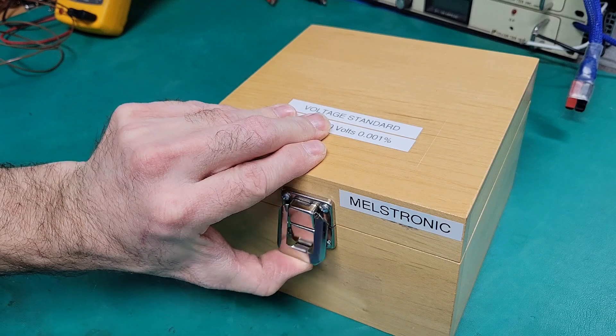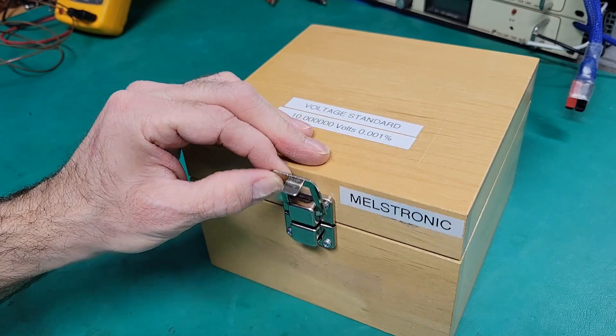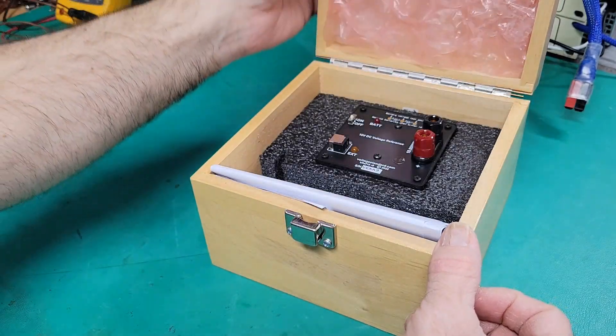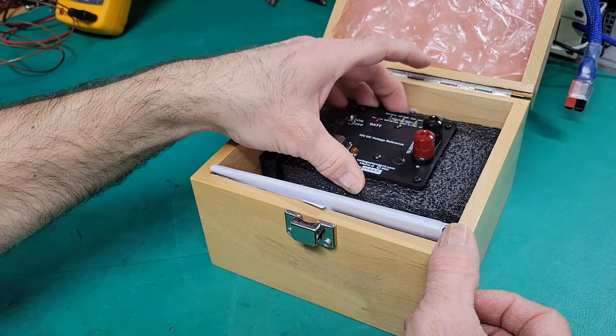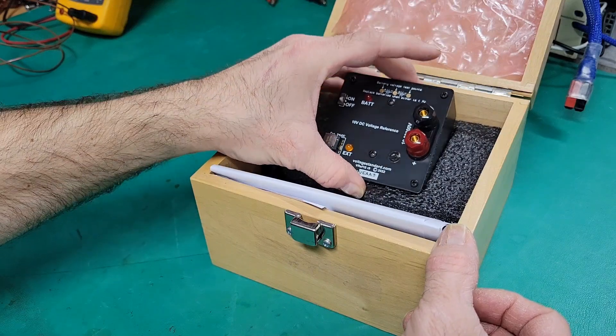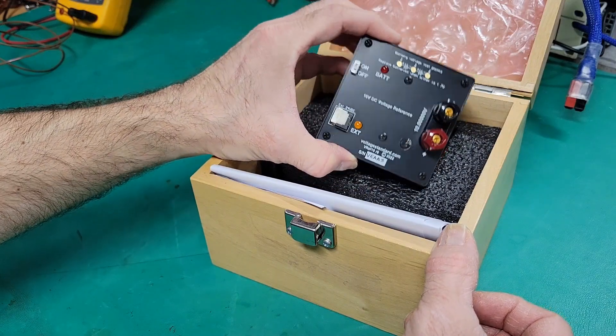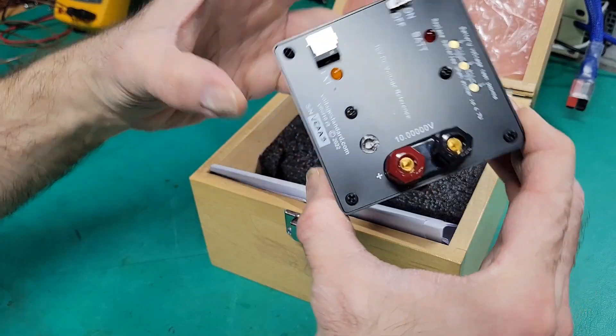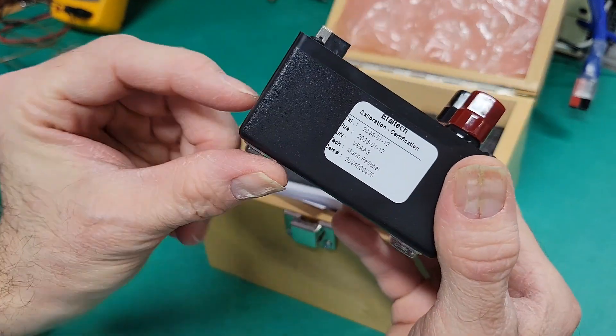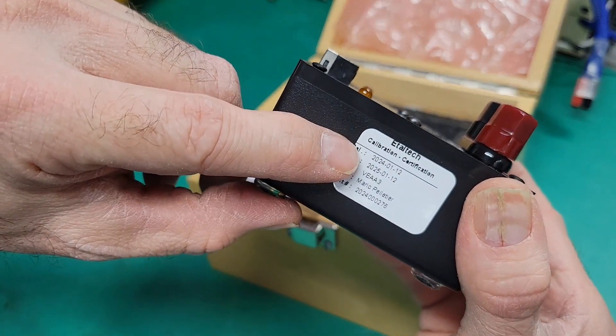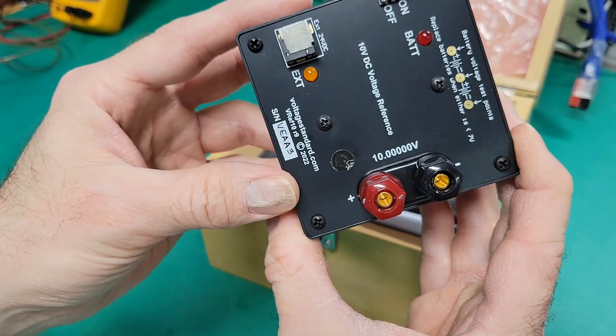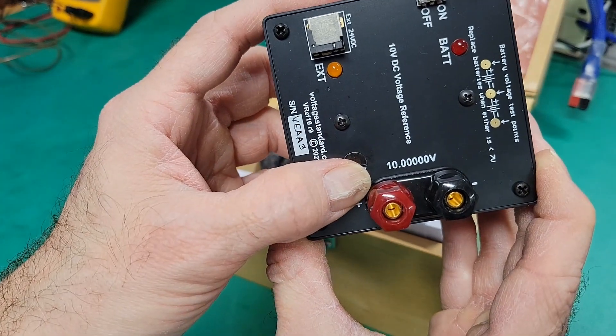In order to do that I first use a voltage standard which I will use to check the voltage calibration of my instrument. So in this case this one is calibrated with the certificate of calibration here, a calibrated 10 volt precision reference.